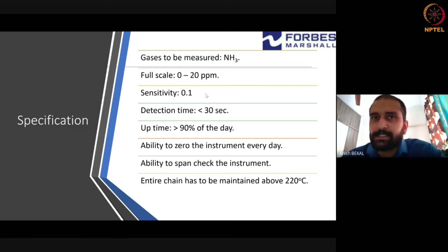The only thing that I want to specify is you're measuring ammonia, and you're at 0 to 20 ppm of concentration, and sensitivity is about 0.1 ppm. Sorry for not putting the unit here. You need as low as 0.1 ppm because people want to keep their ammonia concentrations as low as 2 ppm, because they don't want that to happen and increase the maintenance. Okay, so this is where I was talking about which line is important.